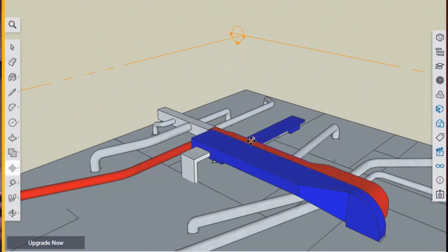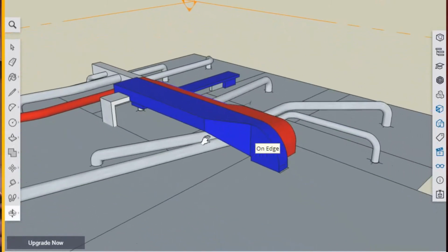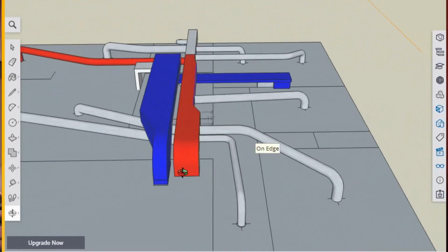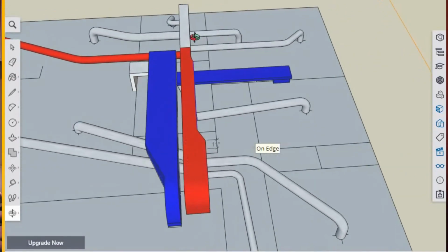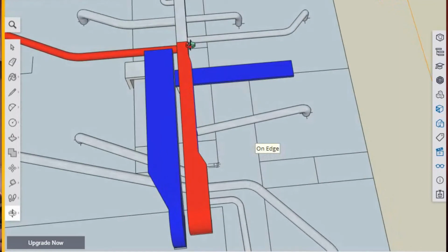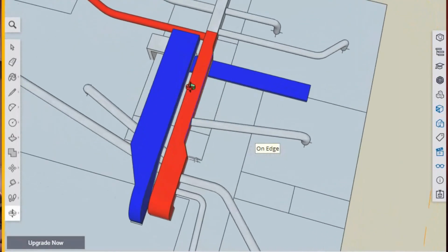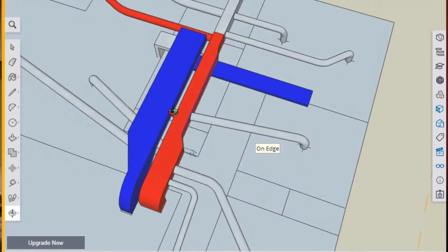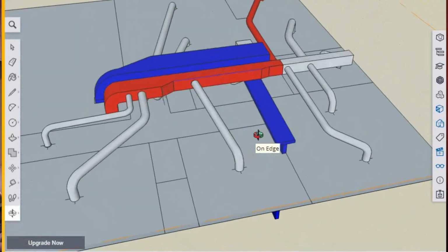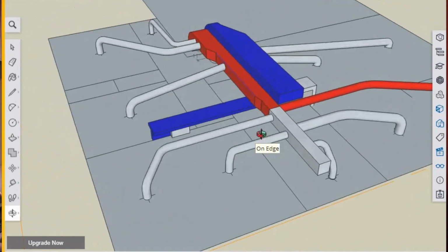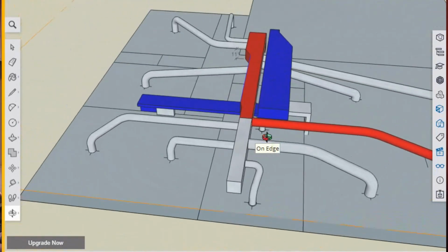Okay, so here is what we've got. We're going to bring our supply up and we are going to shoot it straight down the center of this building. Doing this, running our supply right down the center of our building will keep these duct runs as short and straight as we can possibly get, okay? We're not snaking 30 feet of flex in this direction to a box and then snaking it back over in the other direction to another box. You know, we're going to keep things as short and straight as we possibly can. So if you're using flex, this will be great. If you're using insulated steel, this will even be better.